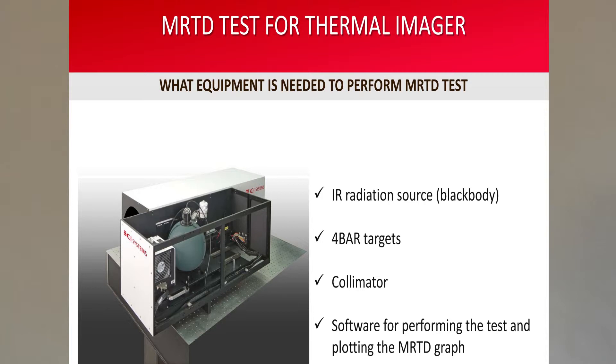To perform MRTD tests, you need the following setup. First, an infrared radiation source, better known as a blackbody. Second, four-bar targets — I will explain about how to select them in just a moment. Third, a collimator. And fourth, the software for performing and plotting the MRTD graph.